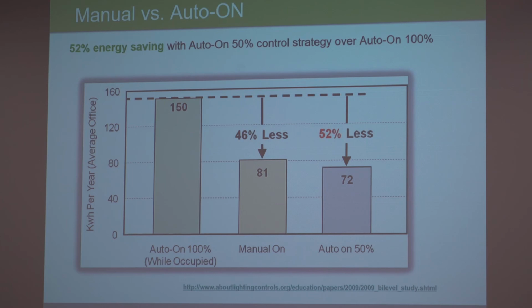Okay, so why do these energy codes require partial automatic on instead of full automatic on, full off, and then even manual on, automatic off? This study shows that manual on sensors, the vacancy sensors, actually save a lot more energy than regular auto sensors. And then the partial automatic on ones even save more energy than the vacancy sensors. Does it sound weird to you guys that partial automatic on actually saves a little bit more energy than manual on, automatic off? Why do you think that is? Someone say it? That's right. So the study basically showed that most occupants were satisfied with the 50% light level, and they didn't turn on the other 50%. So that's why there's additional energy savings there.